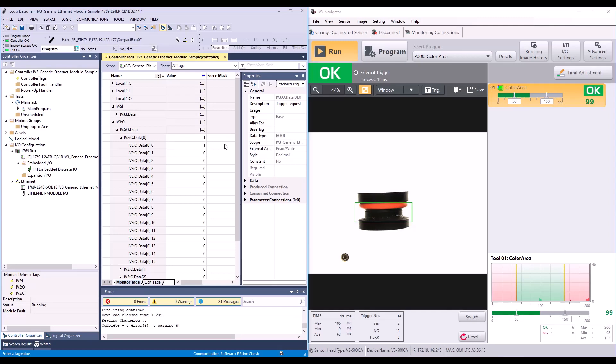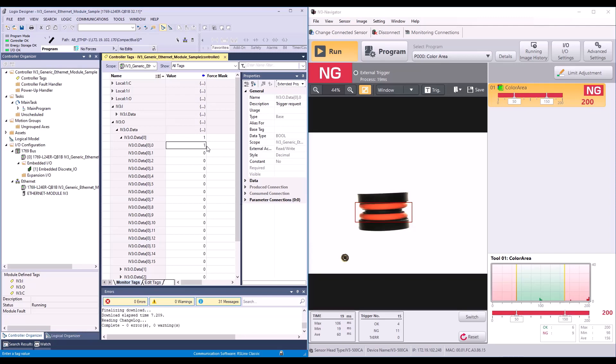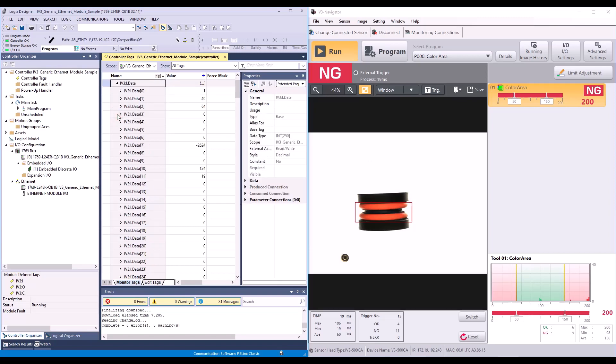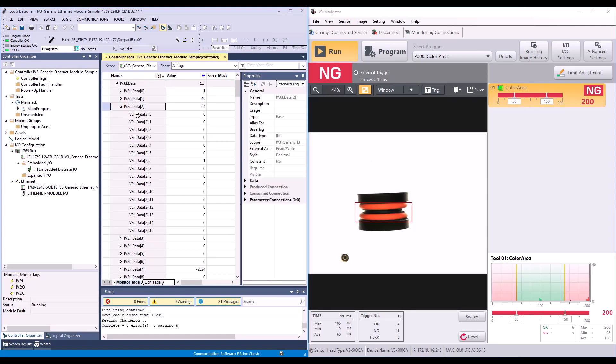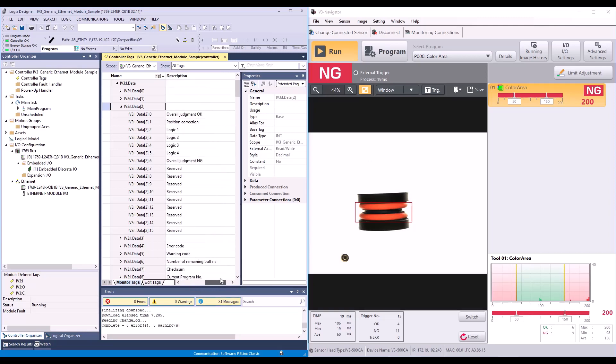Now I'll go ahead and put in a no good part. And I will toggle this bit to a 0 and back to a 1. And we can see it took a new picture here. If I scroll up to my input assembly, my results are going to be in my data 2. So data 2.6 is a 1. And this is my overall judgment no good bit.